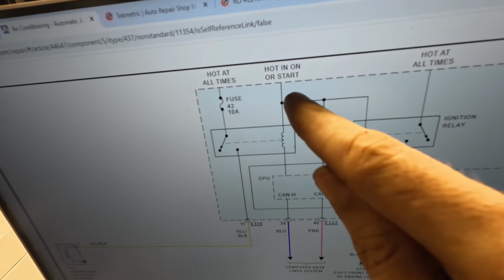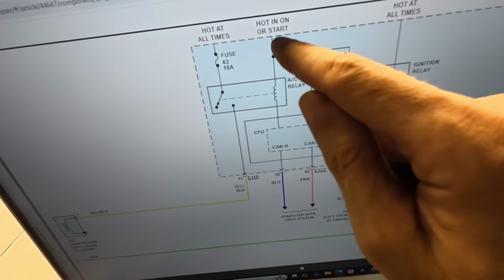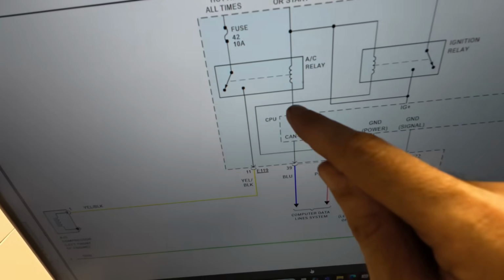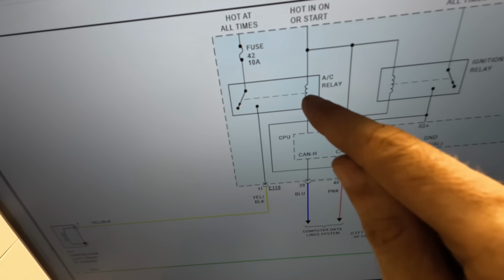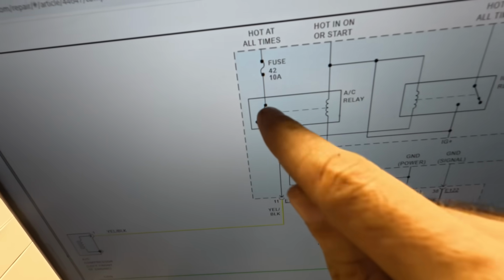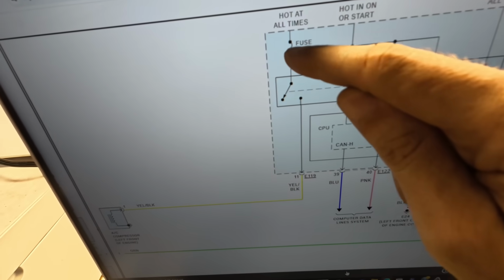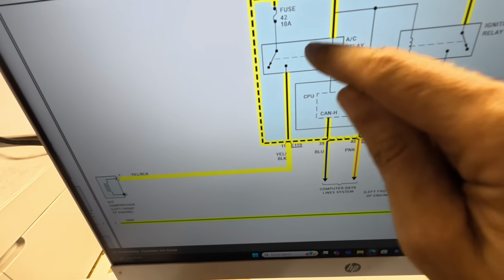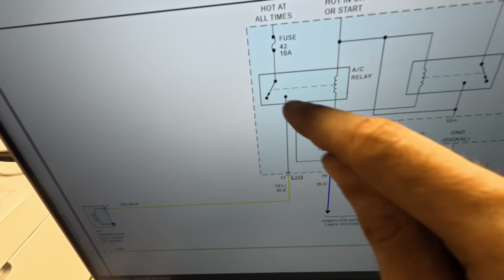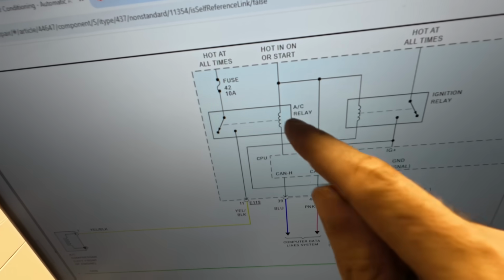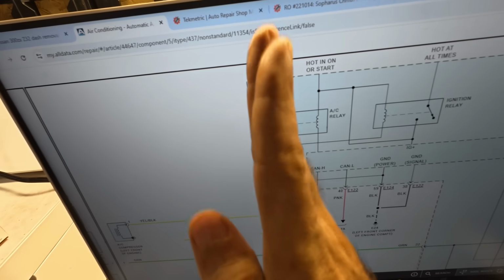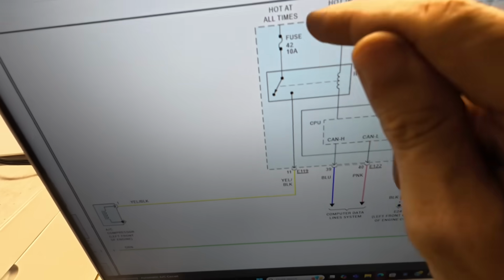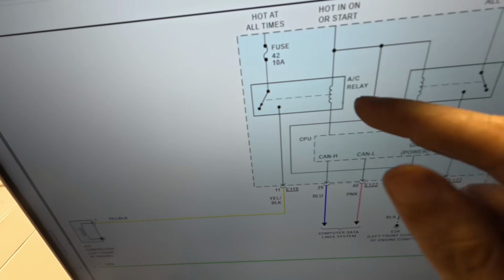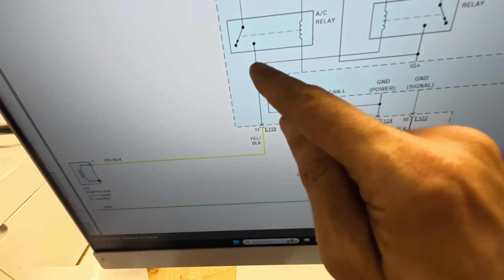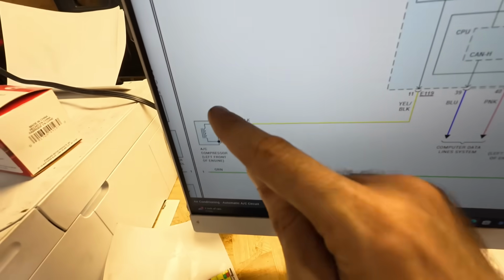Now when we turn on the HVAC module, the button in the dash, that's going to actuate this circuit right here. This circuit is going to close the windings for the switch in the relay and then allow power from the fuse to pass through the relay, because the relay carries the load, not the activation circuit. So you have the activation circuit on one side, then the load carrying circuit on the other side. So we have power supply to the load carrying circuit, but what we do not know is if that power is making its way past the relay and going to the compressor.